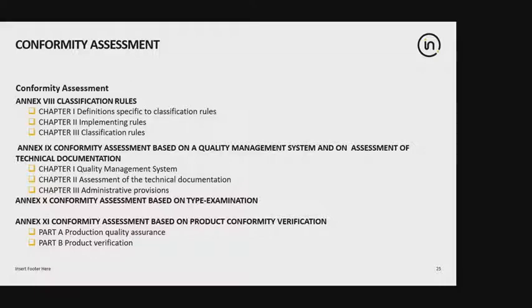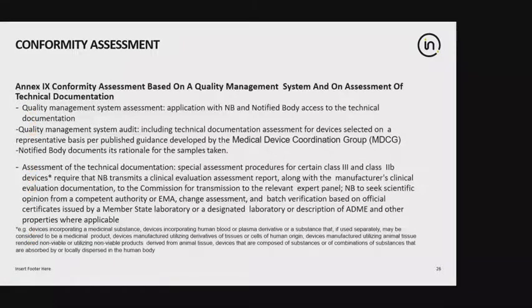The first route is Annex 9, which is a conformity assessment based on a quality management system and an assessment of technical documentation. This is one of the most commonly used methods, where a notified body assesses your quality system and the technical documentation. We will discuss this a little bit further. So for Annex 9, you need to file an application with the notified body, and that notified body assesses the technical documentation for each device category on a sampling basis, or if there is only a single device, then they assess its technical documentation. A quality management system audit is also performed on the manufacturer to ensure compliance with the medical device regulation.